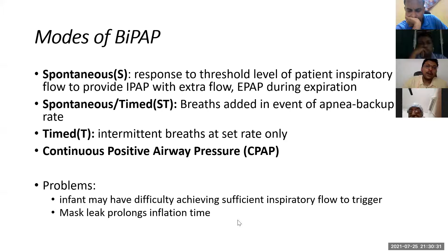The problem with NIV sometimes is that there will be difficulty in the inspiratory trigger. To trigger the machine, the amount of flow which has to be generated, the initial amount of the patient's effort, is sometimes very little. So it will become a problem. That's why we say that NIV should be used only in conscious, alert patients who have their own respiratory drive. Those patients who don't have their own respiratory drive, who are unconscious, we cannot use NIV on them. Okay? And sometimes the mask does not fit well around the face and it can cause leaking, which can cause a lot of problems in machine sensing.